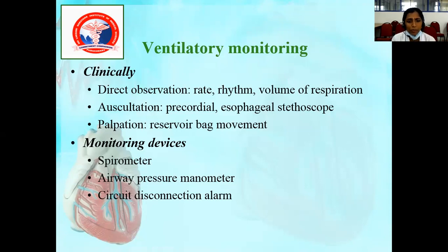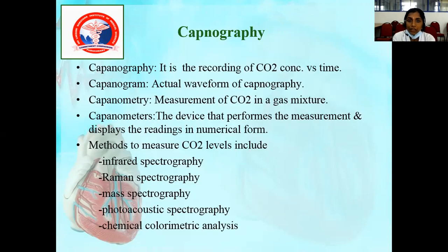Apart from that, we have some special devices also, like a spirometer and airway pressure manometer. And if there is any kind of disconnection in the circuit, you will have a circuit disconnection alarm. Then an important basic monitor is capnography. Capnography is basically the recording of the end tidal expired CO2, which is plotted against time.